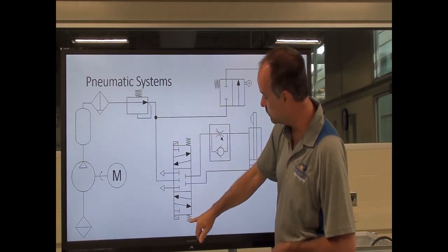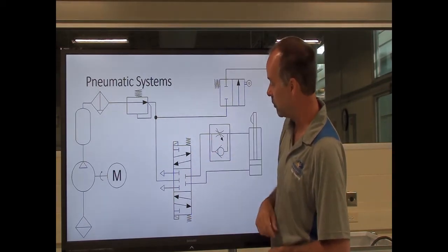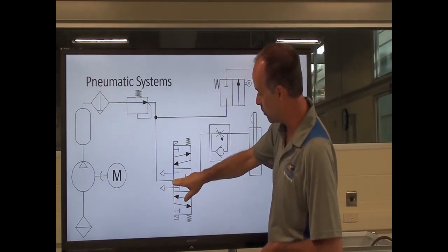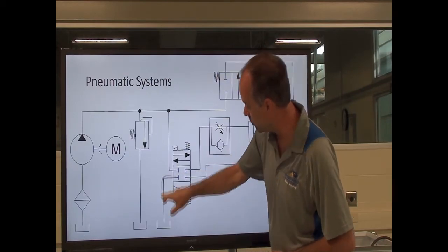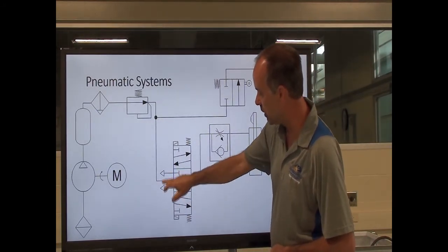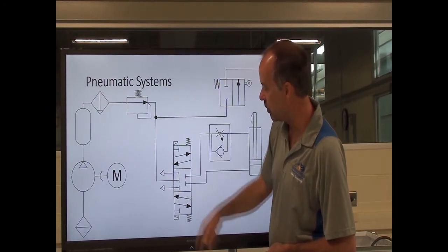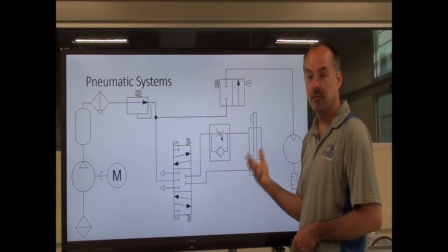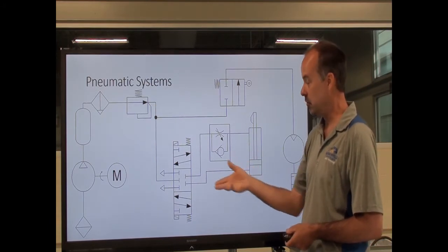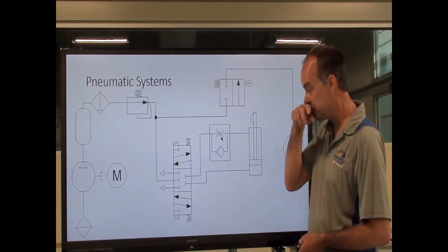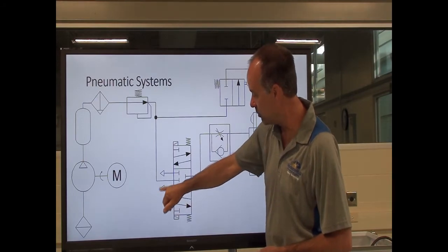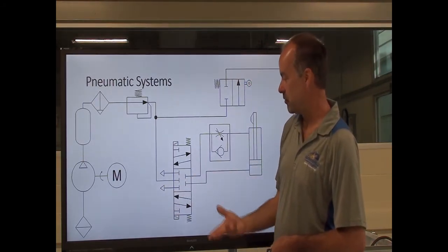The difference is that with the hydraulic system we had one drain port back to tank, but with this valve I've got two exhaust ports. These outlined triangles tell me that air is just exhausted to atmosphere. This doesn't go back to a holding tank — once we're done using this air and it's performed its work, it's exhausted to atmosphere. A line coming off to an open triangle tells me it's going to exhaust to atmosphere.